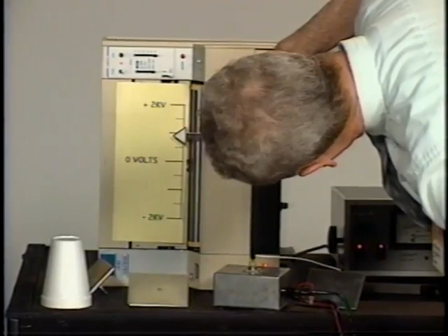To demonstrate this, you see that on the 200 volt range here, we are past 200 volts. So voltage-sensitive devices would have a real problem with this length of wire. We'll take an ionizer over here, and we will turn the ionizer on and watch the discharge rate. You're also hearing it on the radio, so I will shut the radio off.